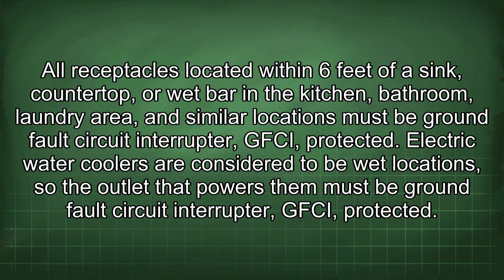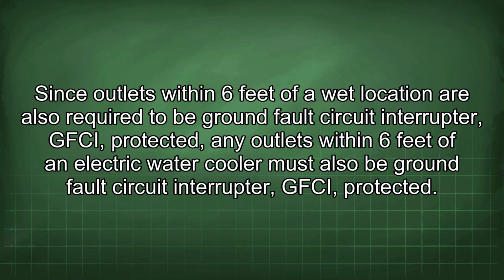Electric water coolers are considered to be wet locations, so the outlet that powers them must be GFCI protected. Since outlets within 6 feet of a wet location are also required to be GFCI protected, any outlets within 6 feet of an electric water cooler must also be GFCI protected.